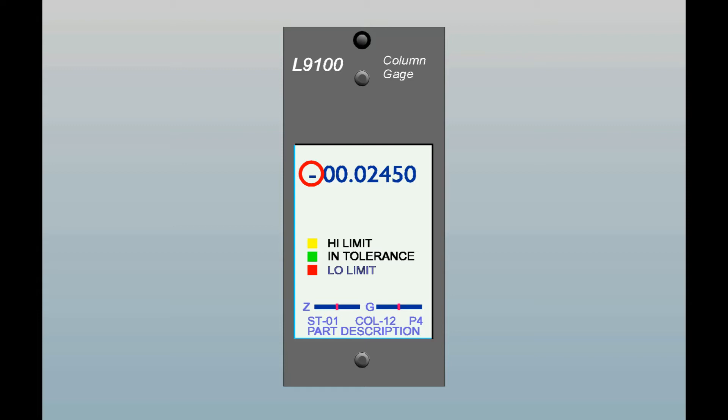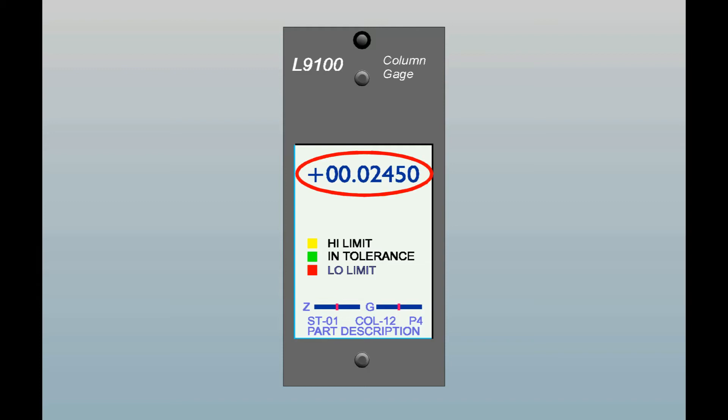In actual size mode, if a nominal part size is programmed in, then it will always be positive. If the column is programmed for imperial operation in inches, there will be two digits before the decimal followed by another five digits. If programmed for metric operation, there will be three digits before the decimal and four digits following.